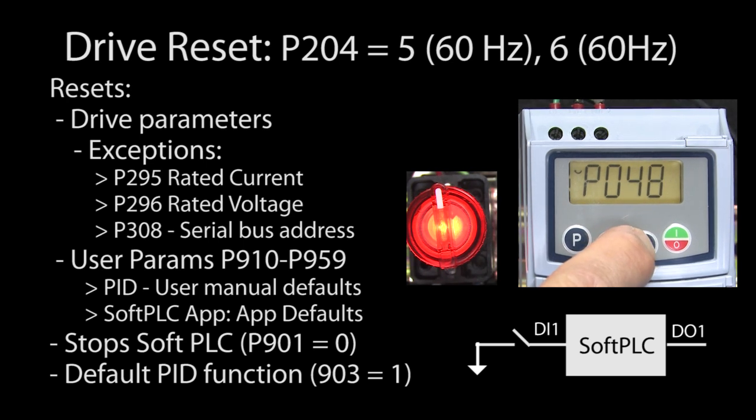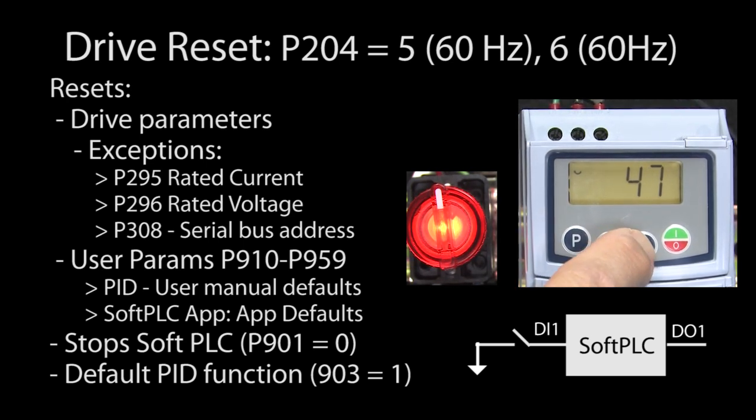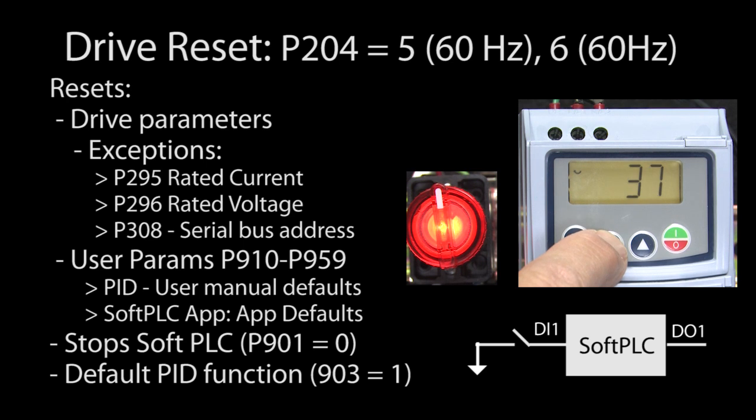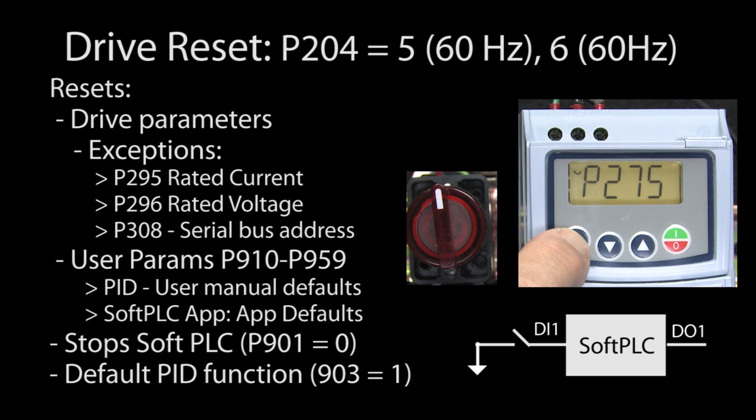Since we reset the drive parameters, we need to go back to drive parameter 275 and set it to a 37. That tells the drive that digital output 1 is being used by the soft PLC.